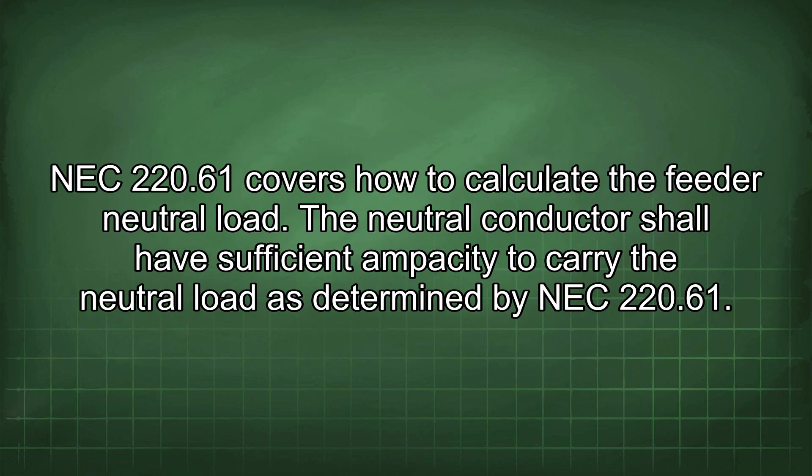NEC 220.61 covers how to calculate the feeder neutral load. The neutral conductor shall have sufficient ampacity to carry the neutral load as determined by NEC 220.61.